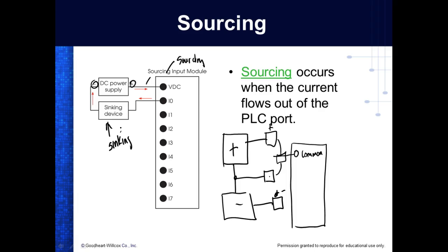Or now you blame the PLC. You say, well, it must be the PLC that's bad. Then you replace your PLC, right? You understand? Then you do what? You hook up the sensor and it's still bad.